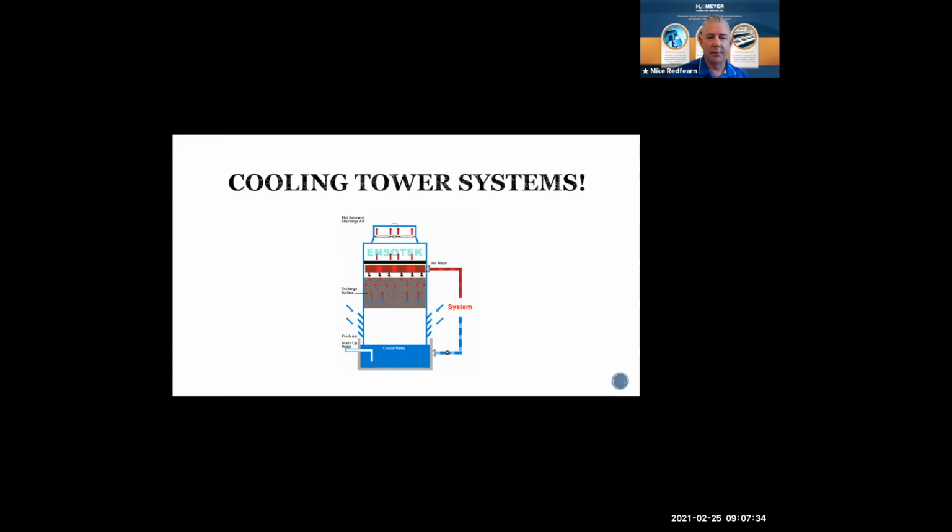But this is one place. The problem is that cooling tower systems are generally designed, treatment-wise, with a consistent makeup. And sometimes when you're using reclaimed water, you get a lot of variability. You don't know what consistency the water is going to be today as it is going to be in another season, and you set up your programs designed around a specific makeup quality. Next slide.